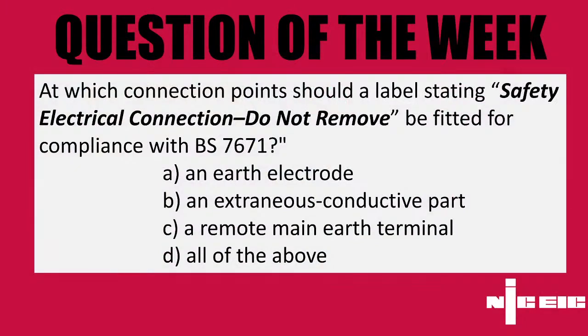So I'll just remind everybody about our question of the week. We posted this out earlier today. Our question of the week was around: at which connection points should a label stating "safety electrical connection, do not remove" be fitted for compliance with BS 7671? And the options given were the connection to an earth electrode, the connection to an extraneous conductive part, the connection to a remote main earthing terminal, or is it all of the above? And the answer is all of the above.